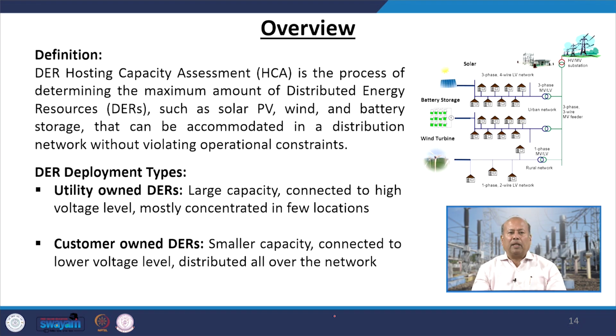DER deployment types: utility owned DERs, large capacity, connected to high voltage level, mostly concentrated in a few locations. Customer owned DERs, smaller capacity, connected to low voltage level, distributed all over the network. And you will be happy to know that at the IIT Roorkee distribution network, not only do we have 2.7 megawatt of PV at 35 different locations, but we also have two storage units connected at two different locations of the campus.